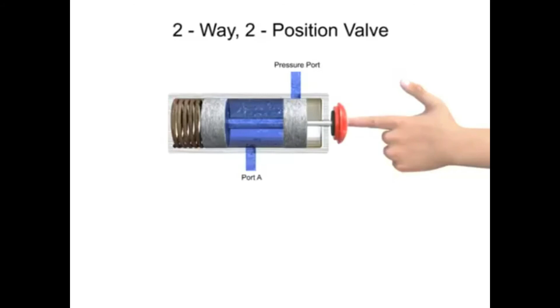Boxes, sometimes called envelopes, are used to indicate the number of valve positions. Since this is a 2-position valve, its graphic representation has 2 adjacent boxes. Continuous lines are used to indicate fluid flow between ports. For complex valves, the ports may also be labeled. The input port is typically labeled P for pressure.